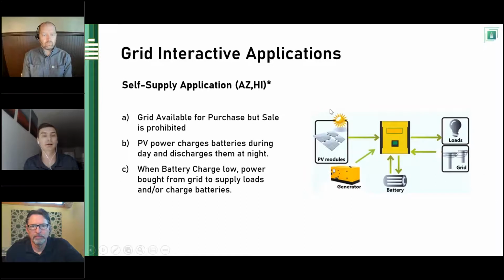The other application we're seeing is a self-supply application. Looking at the chart, you're able to purchase from the grid, but not able to sell back to it. So any excess PV made after the battery is charged can't be net metered. The PV power charges the battery during the day, if the loads are already being powered by the solar, and then it discharges the battery at night. So you're maximizing your full PV production here, since you can't sell it back for credits from the utility company.